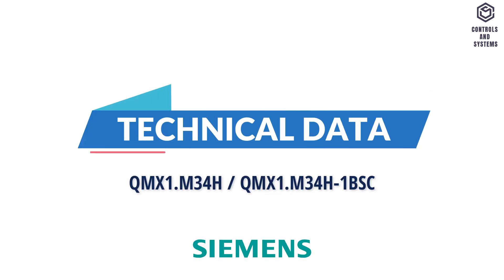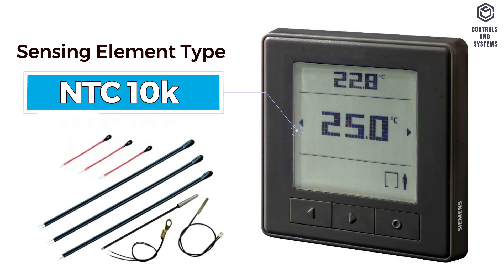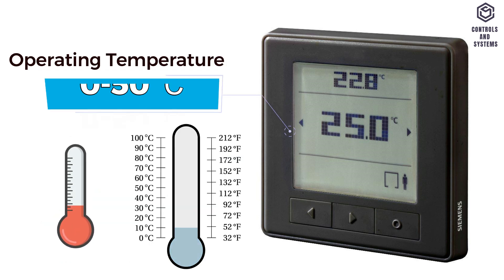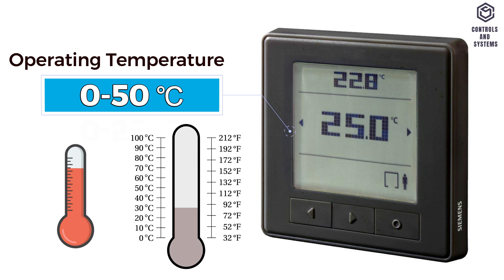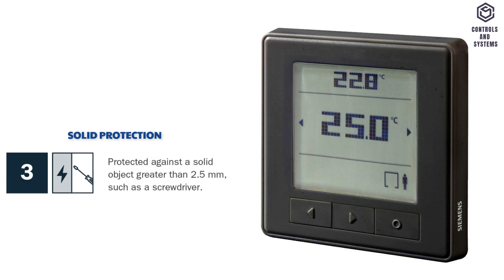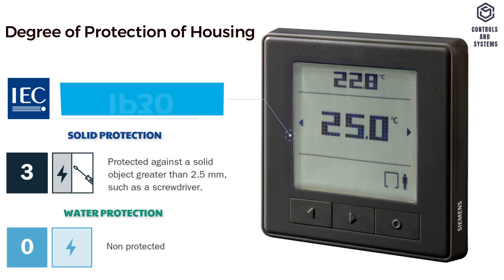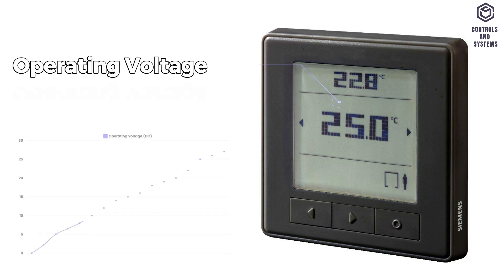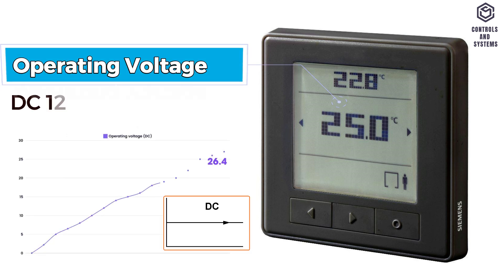Technical data: sensing element type is NTC 10K, operating temperature is 0 to 50 degrees Celsius, degree of protection of housing to IEC EN is IP 30, operating voltage is DC 12 to 26.4 volt, 5 milliamps.